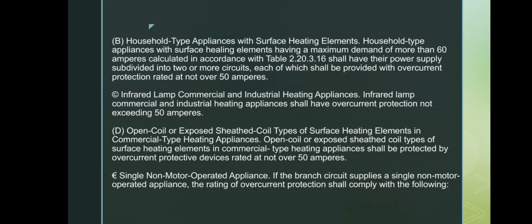Next, let's talk about the overcurrent protection requirements for different types of heating appliances. First, for household appliances with surface heating elements that have a demand of more than 60 amperes, the power supply needs to be split into two or more circuits, and each one must have overcurrent protection rated no higher than 50 amperes. Second, for infrared lamp heating appliances used in commercial or industrial settings, the rule is simple. They must also have overcurrent protection not exceeding 50 amperes.